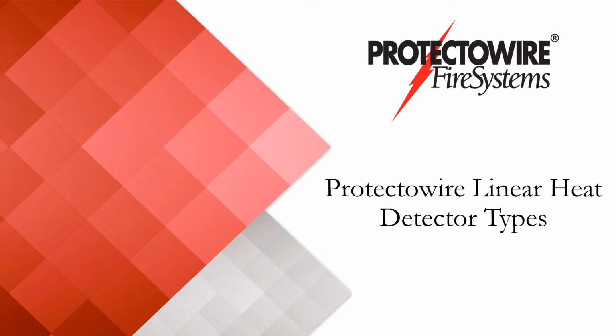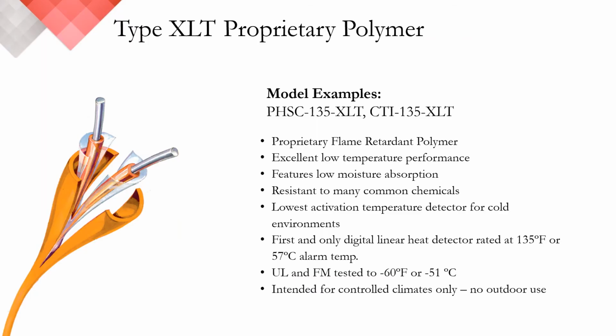Now we can move on to choosing the correct Protectowire linear heat detector for your refrigerated or freezer warehouse. Protectowire currently offers 8 different fixed initiation temperatures, ranging from our lowest activation temperature at 135 degrees Fahrenheit or 57 degrees Celsius to our ultra-high 500 degree Fahrenheit or 260 degrees Celsius detector. Today we're going to focus on our XLT series. XLT stands for extremely low temperature. We offer this detection temperature in 2 different technologies, our standard PHSC and our newer CTI technology. I'll discuss these in detail in the next few slides.